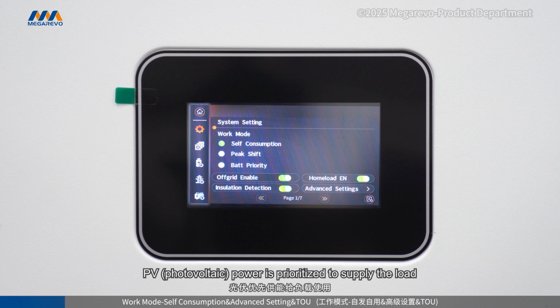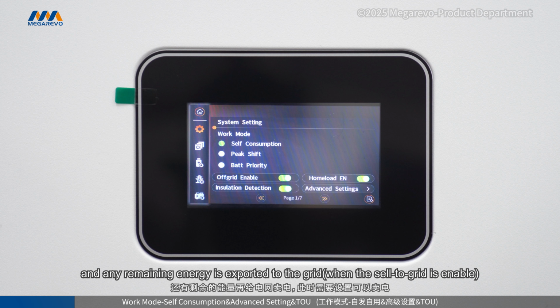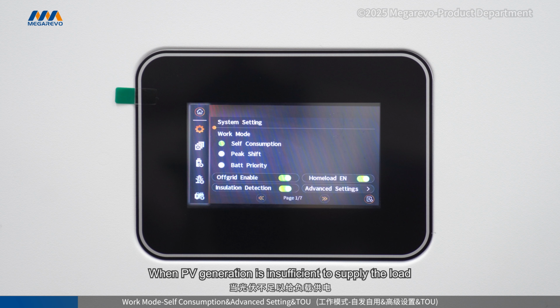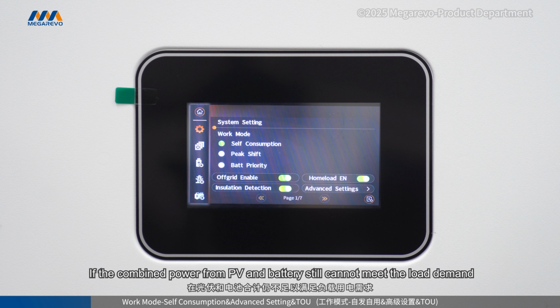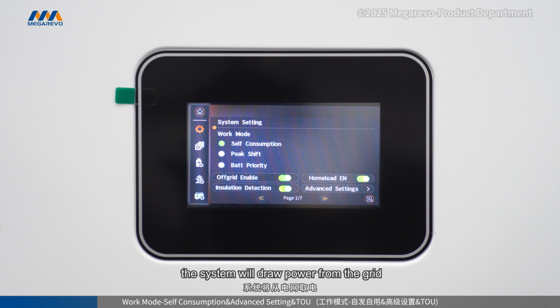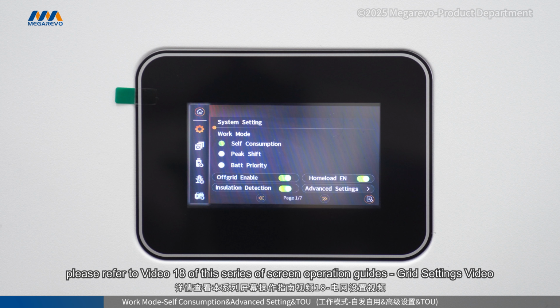PV power is prioritized to supply the load. Surplus energy is used to charge the battery, and any remaining energy is exported to the grid. When PV generation is insufficient to supply the load, the remaining required power will be drawn from the battery first. If the combined power from PV and battery still cannot meet the load demand, the system will draw power from the grid. For details, please refer to video 18 of this series of screen operation guides, grid settings video.